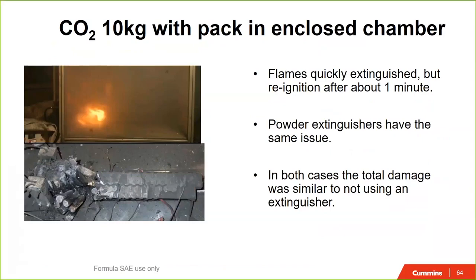So we put this in a fish tank and put it out with a CO2 extinguisher. The CO2 extinguisher will knock the flames down, enabling you to get past that pack to evacuate. But it will generally reignite because you can't take enough heat out of the cells, and they just create their own oxygen and then restart and reignite.